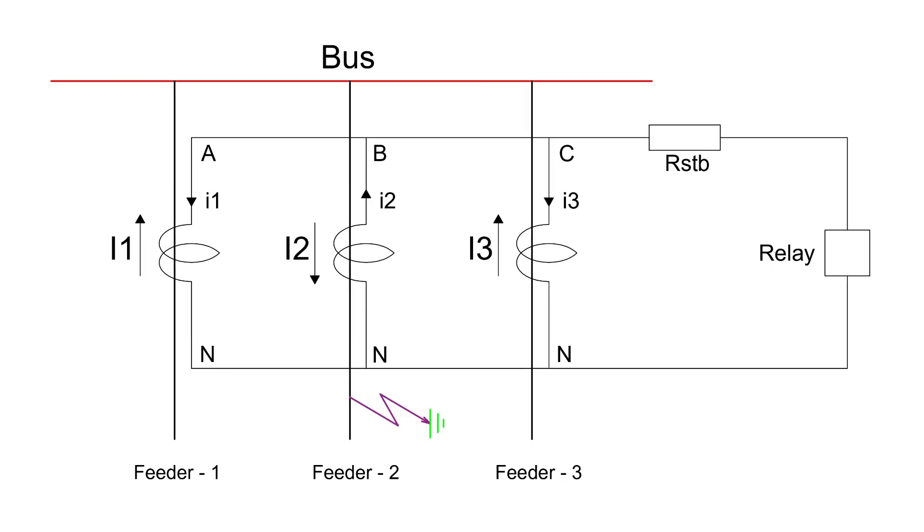Now let's consider a through fault, which is a fault occurring outside the protection zone. Suppose a fault occurs after the CT of any feeder. Ideally, if all CTs maintain the same nominal ratio for all external faults, no current will flow in the relay coil. However, in practical cases, the relay may falsely operate due to a reduction in the nominal ratio of the fault CT resulting from CT core saturation. This false differential current can trip the relay incorrectly.